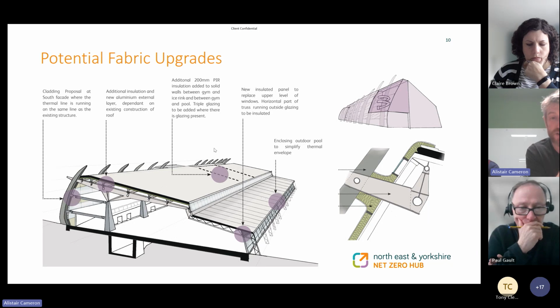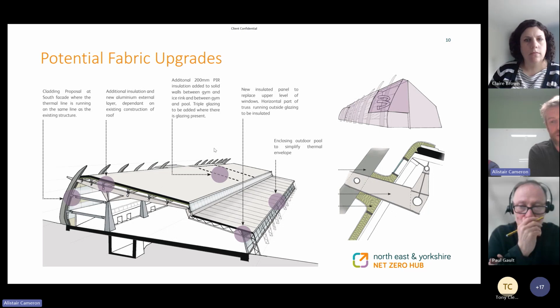And that's actually leading to corrosion of the steelwork on the inside of the building as well, just because of the temperature delta between the two of them and the moisture as well. So there are solutions to potentially overclad or wrap some of these elements here to stop that thermal bridge, and that would be fairly easy to do. When they retrofitted the ice rink into the building as well, they didn't actually install any insulation into the walls which separate the ancillary spaces from the ice rink. So you've essentially got a constant sort of 2-degree temperature within the building that's just putting coolth into the rest of the building. So we can tackle that by installing insulation into the internal walls. And in terms of the differential between the warm space, the cold space, and the hot space, which I showed in the diagram previously, again, there's no insulation internally in these walls.